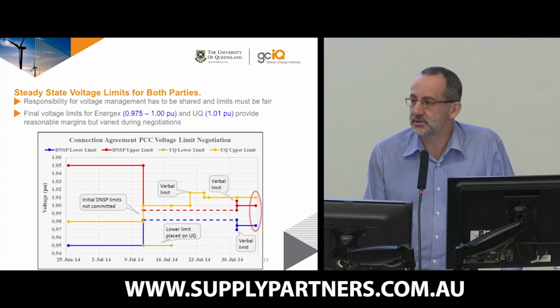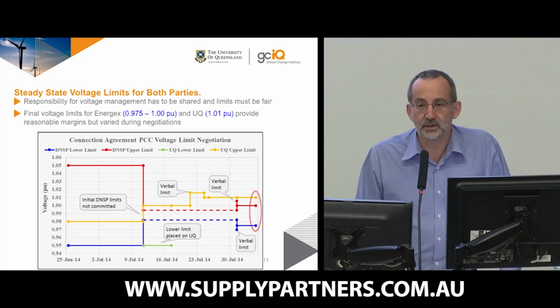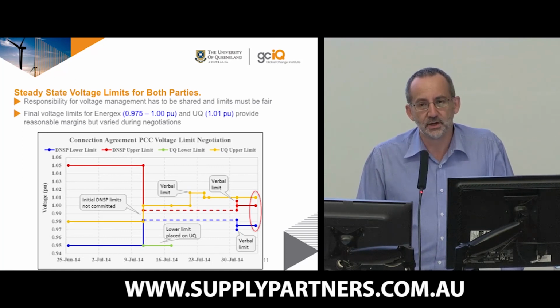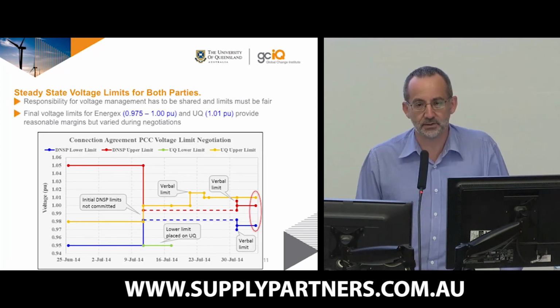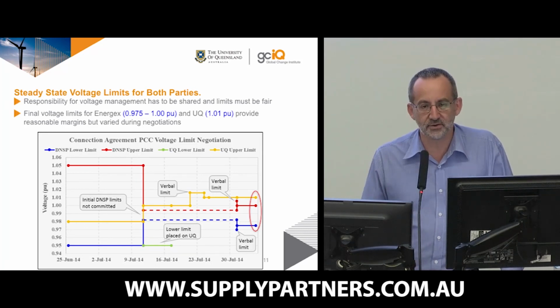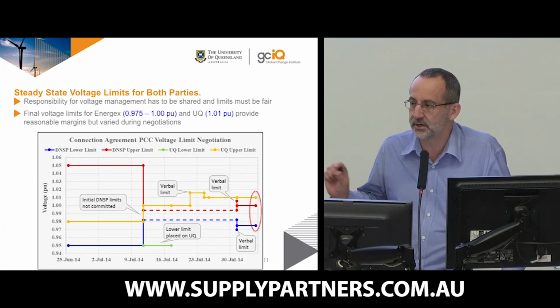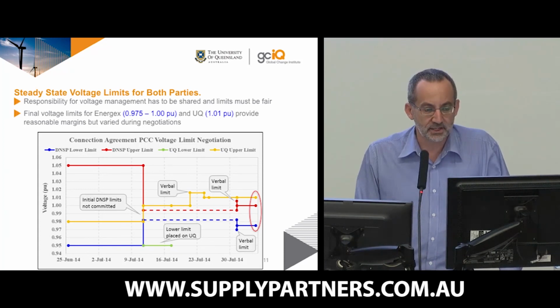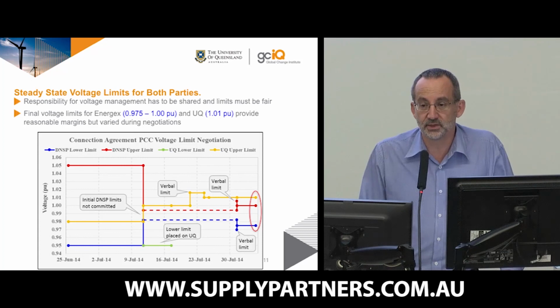As you probably realise, across the network, the utilities are allowed in Queensland a 10% variation on the 11 kV, the 11,000 volt network. That's quite a wide range, and they need that wide range, but they don't want to be varying that range at any point on the network. And in fact, they still need to be controlling it fairly tightly at any particular point. So Energex ultimately agreed to hold the voltage within 2.5%. And when we come on, we've agreed not to raise it by any more than 1% above that.